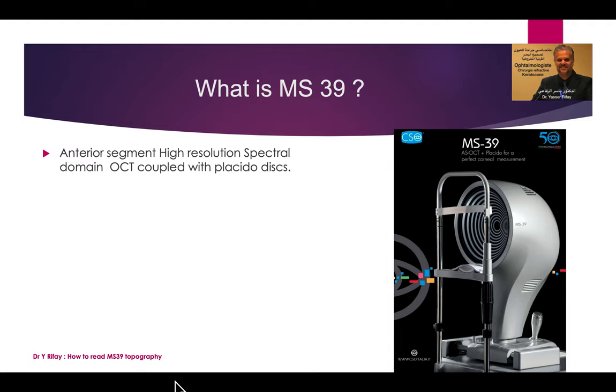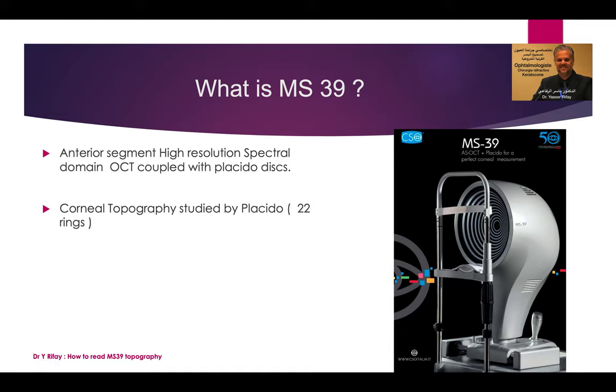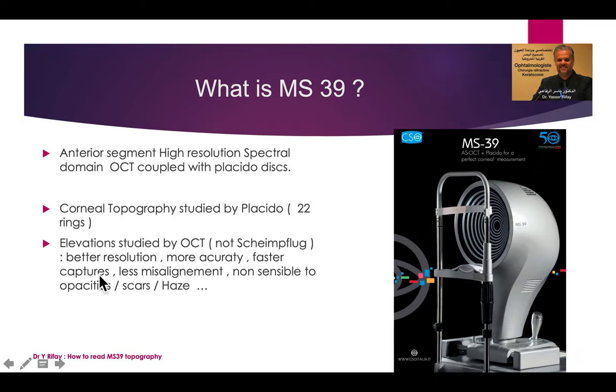What is MS-39? It's an anterior segment high resolution spectral domain OCT coupled with Placido discs. Corneal topography is studied by Placido 22 rings. Elevations are studied by OCT, not Scheimpflug like Sirius or Pentacam. It gives better resolution, more accuracy, faster captures, less misalignment, and is non-sensitive to opacity, scars, and haze.